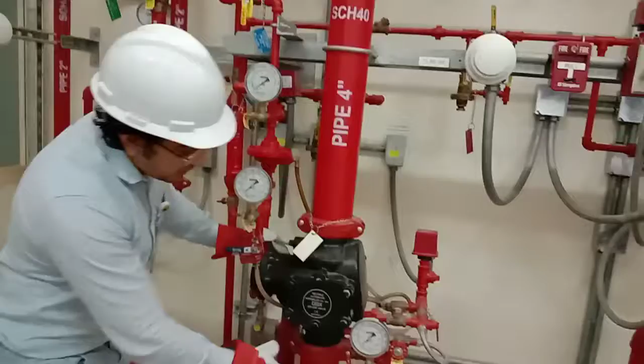Now, coming to the components and working principle of the deluge valve, right? As I said, the deluge valve has open sprinklers, right? So we don't have air inside the piping. It is just closed, and from here we are getting water, right? Let's start with the control valve. We have a butterfly control valve, which has a placard saying riser group 1 deluge control valve, right? If you can see, the indicator is saying the valve is open now because it is perpendicular to the pipe. If it is parallel to the pipe, it means the valve is closed.